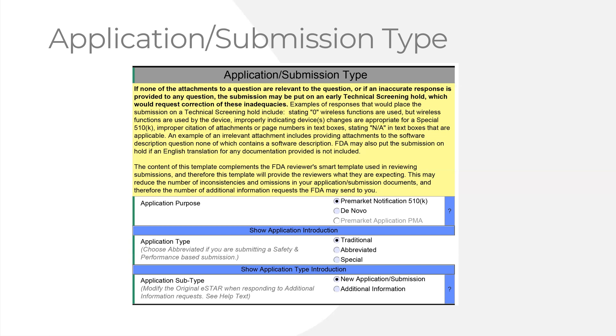For application type, you have two options: a new submission or additional information. You submit, they do a technical review, and in about 15 days they send an email saying your reviewer has been assigned and they're starting substantive review. The next communication comes at 60 days from your initial submission date — either an AI hold for additional information request, or an email saying you're in interactive review. If they send a deficiency letter requesting additional information, when you respond you click 'additional information' and submit using the eStar template, removing obsolete items, uploading new ones, and addressing their concerns.